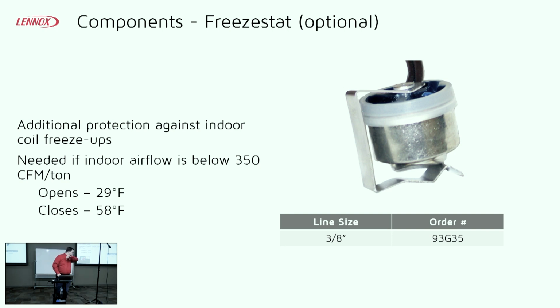So Freezestat, excuse me, that's another optional feature. Of course, that's just to protect the coil if we're running, especially as we slice these up into more zones, the less airflow we have. Sometimes guys fly a little bit too close to the sun with some of this staged equipment where, even on low stage, we'll see it happen where, okay, you've got a 3-ton outdoor unit, something like an XC16, even on first stage, it's doing 2 tons.